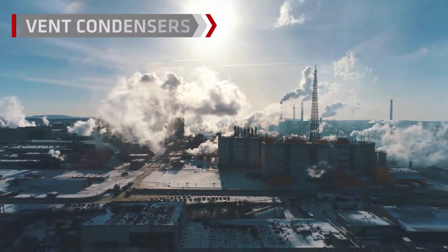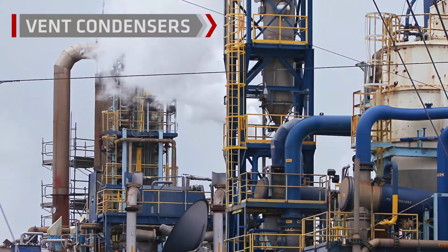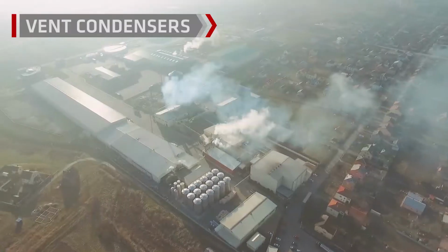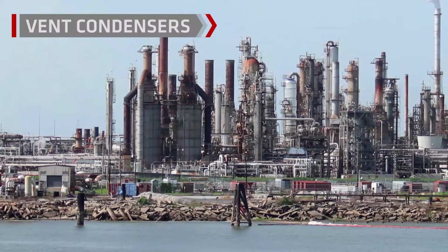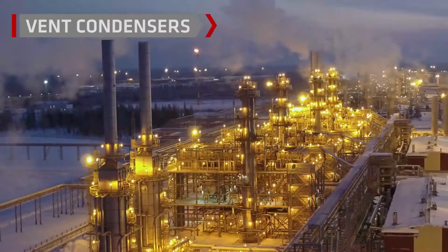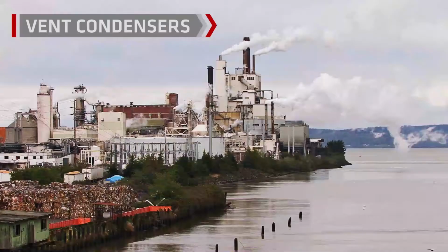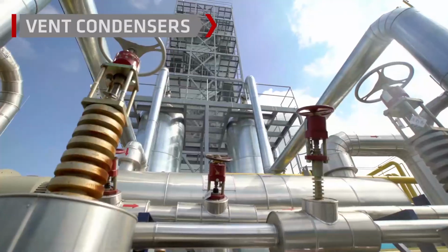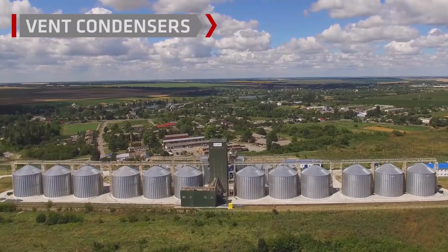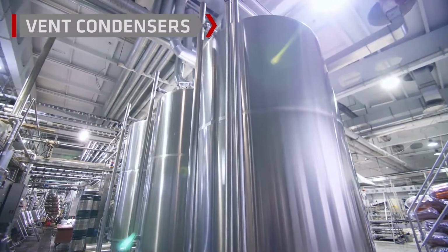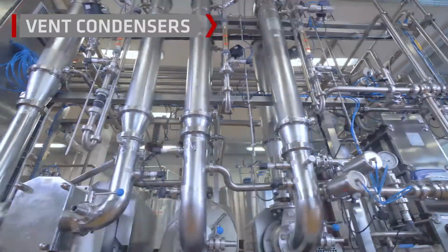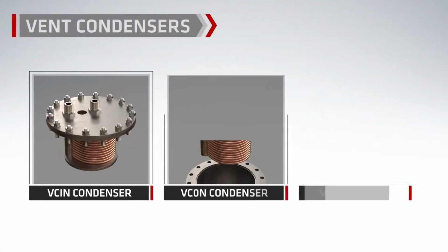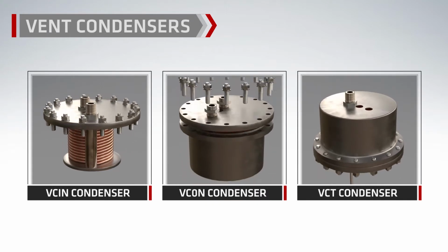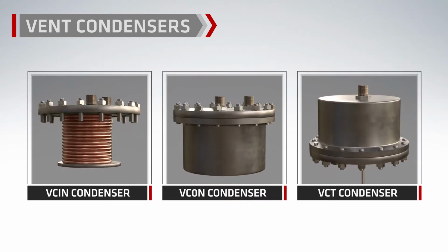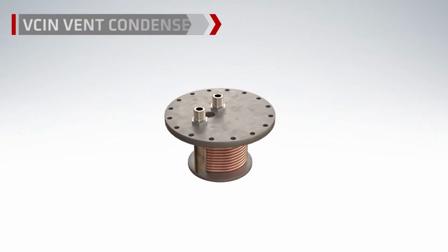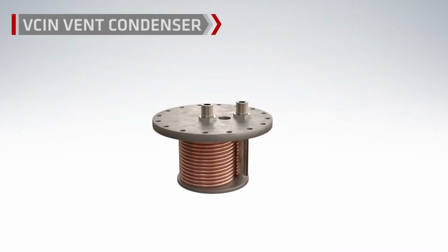The Heliflow is utilized as a vent condenser to reduce VOC emissions. By recovering the VOCs before they are emitted to atmosphere, a plant can meet stringent emissions regulations while recovering valuable process liquids for reuse. Most Heliflow vent condensers can be installed on existing tank vents or columns without the need for additional support. The Heliflow can be applied as a vent condenser in 3 different styles: the VCIN, the VCON, and the VCT. VCIN denotes Vent Condenser Inside Connection.